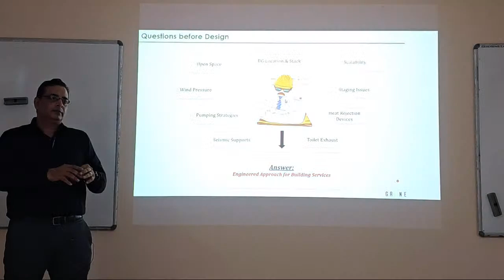So when you back up a building with a DG, the diesel generator, that's 100% backup. The problem is, where do you locate them? And if you locate them within a building, you've seen some stack that needs to come — that's a stack, it's a flue pipe. The flue pipe comes within the building line and goes right up to the building top. That's a critical design consideration within a tall building.